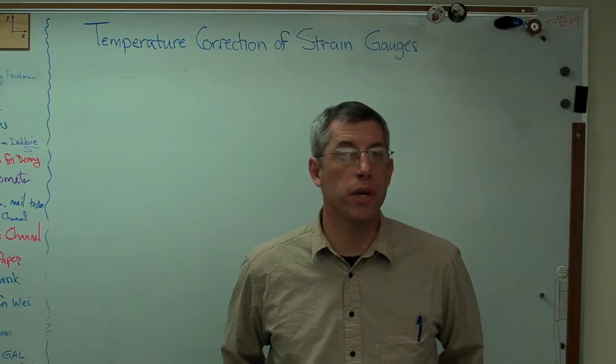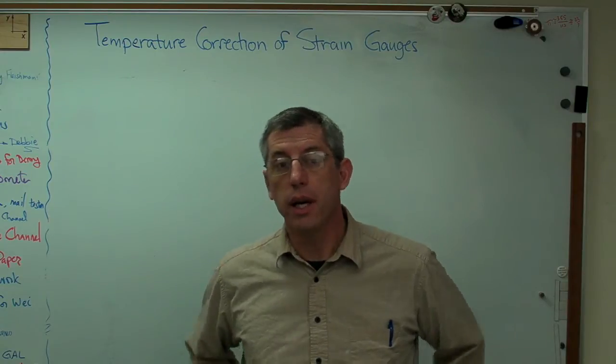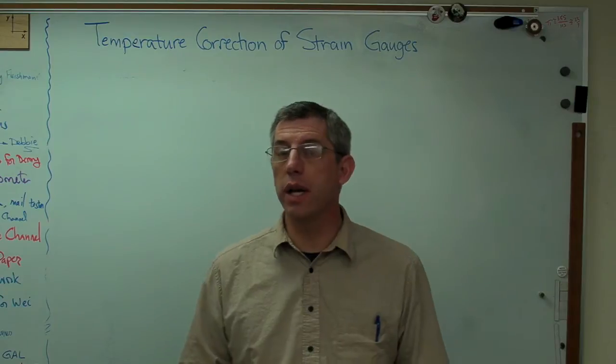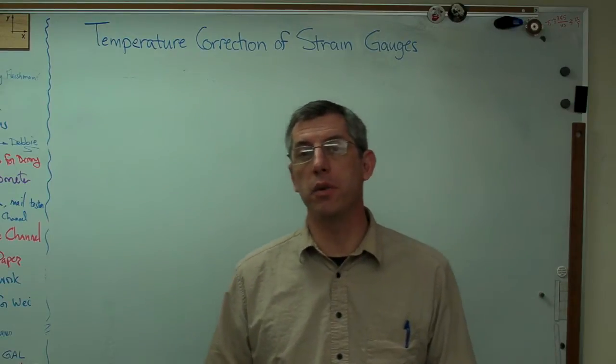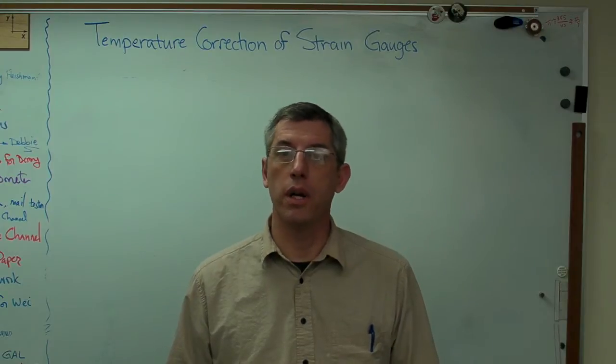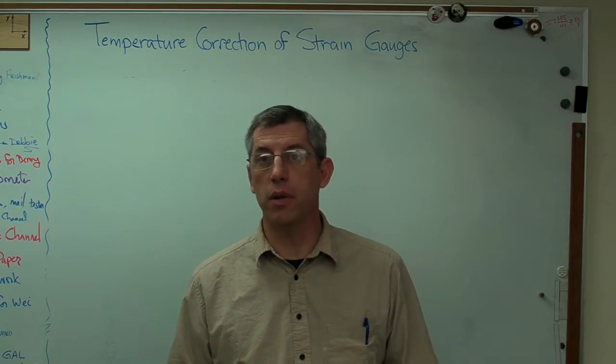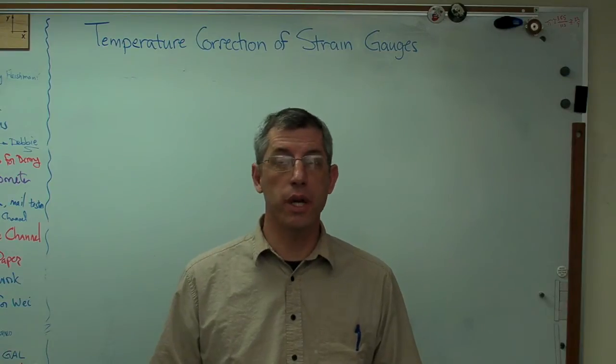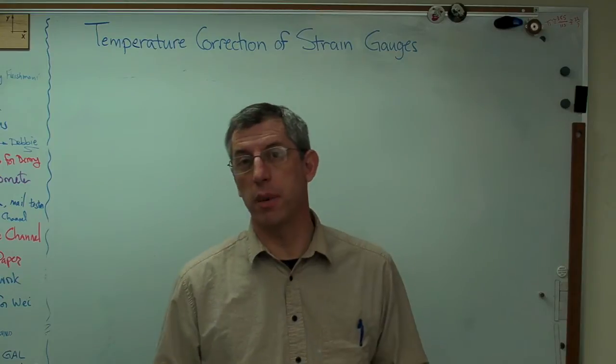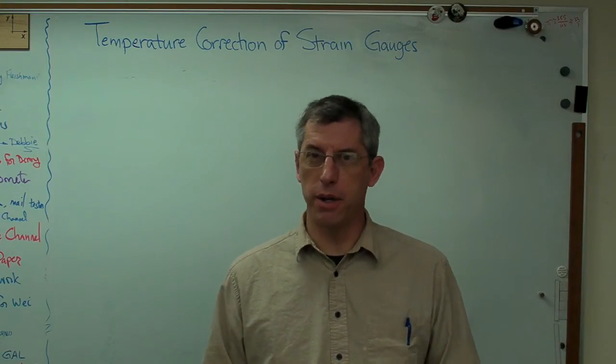Temperature change between when you apply the strain gauge and when you're measuring data from the strain gauge. The reason this is important is because strain is strain. The strain gauge does not know the difference between strain coming from a load and strain coming from a temperature change. There are many times in which we want to make sure that the strain gauge measures only the strain due to a load and does not respond to a temperature change, or vice versa. We can do either one. So that's what I want to talk about here.